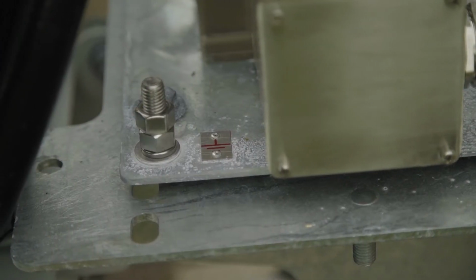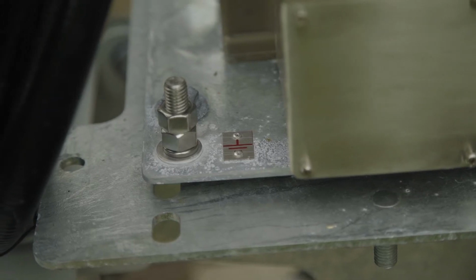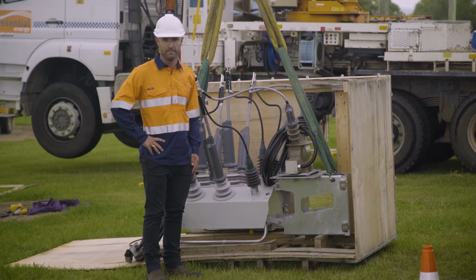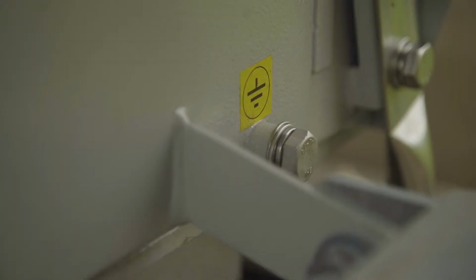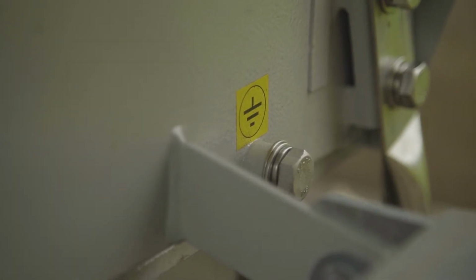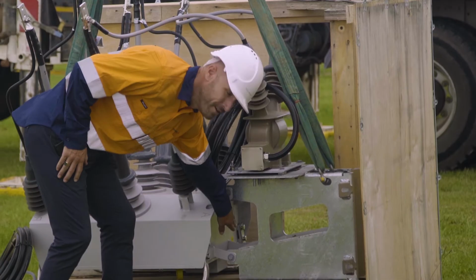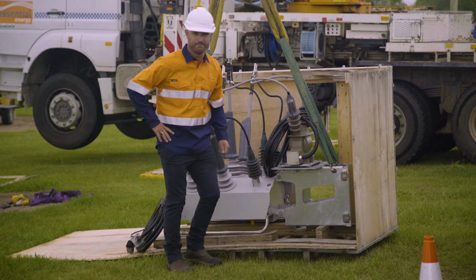NOJA Power recommends a 35mm earth or greater, and all earthing points must be earthed. All earthing points are marked, and we have an earth point on our VT and on the back end of our switch.